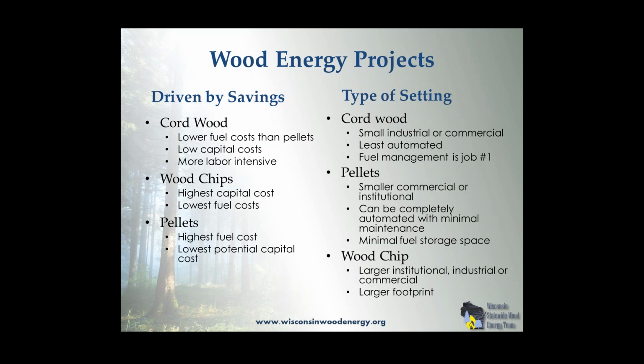Wood chips have the highest capital cost, but they also provide us with the greatest opportunity for return. And pellets are very automated. They can be more automated than wood chips, actually. They almost always have the potential for self-starting, which gives them a little more flexibility and range of load that they can cover, and sizing of systems. But they also have a lower fuel opportunity cost. Right now, pellets in the east, at least, when you compare that to propane, there's not much fuel advantage or fuel cost savings. So, you're limited to going against fuel oil, and so it kind of limits the market when there's not a lot of savings with pellets. Those are some of the challenges with trying to implement systems.